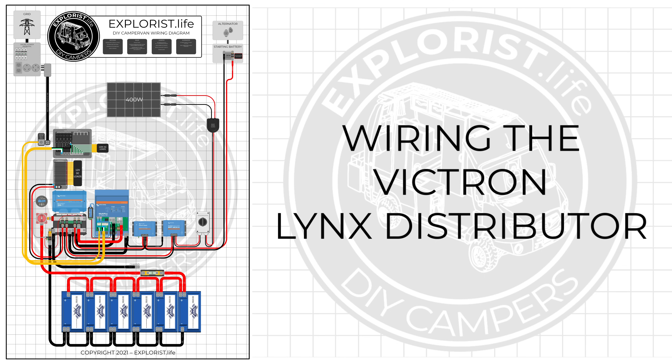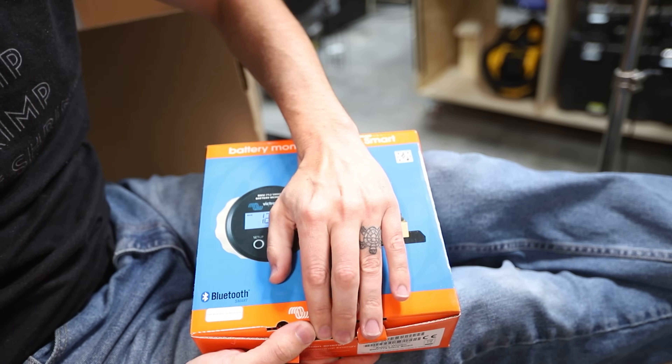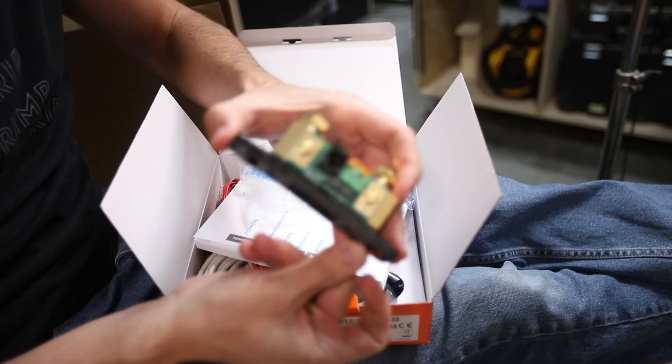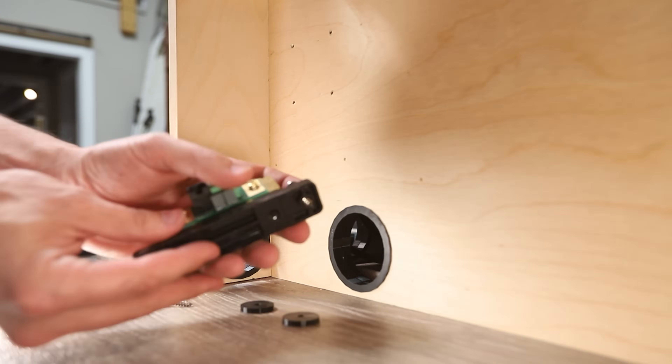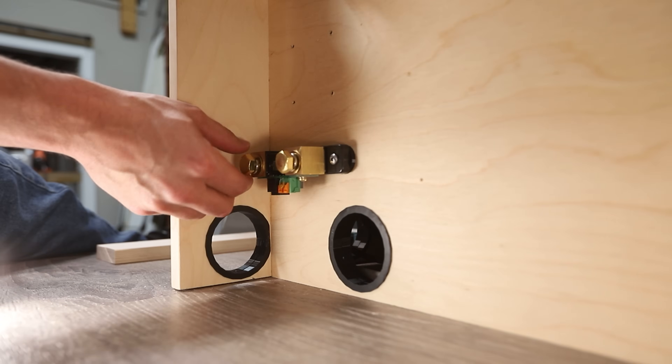Now it's time to connect the battery bank to the Victron Lynx distributor. Components used include the Victron Lynx distributor and the EXPLORIST.life Lynx distributor wiring kit, which includes the Victron BMV 712 battery monitor, wire, wire lugs, heat shrink, an ANL fuse and fuse holder, Lynx adapters, a master battery disconnect, shunt and switch spacers, a butt splice connector, and assorted screws and hardware. The first step is mounting the shunt — I thoroughly read the instruction manual, then grabbed the shunt and spacers from the kit. With the shunt position pre-laid out from the enclosure build, mounting it was simply a matter of screwing it to the wall with spacers between.